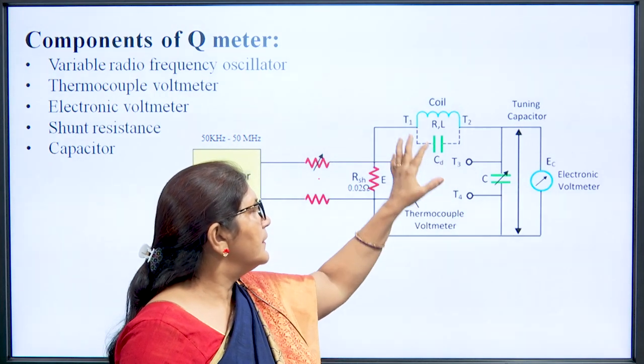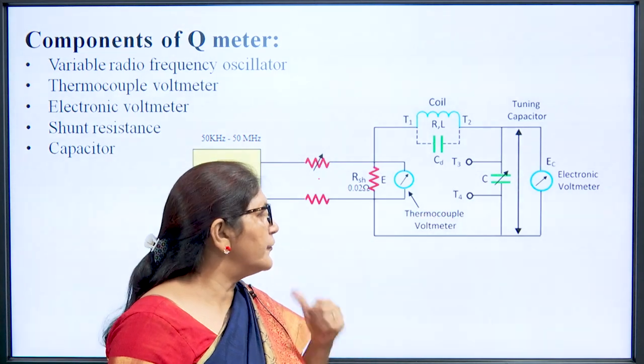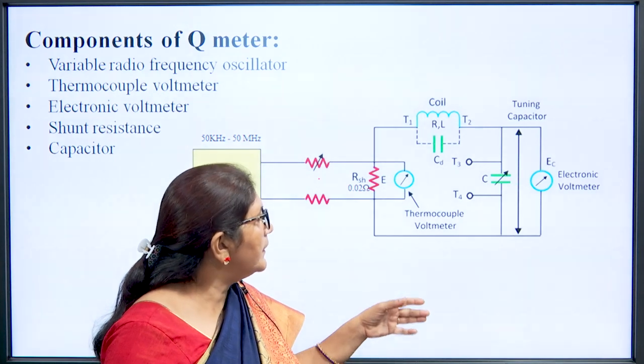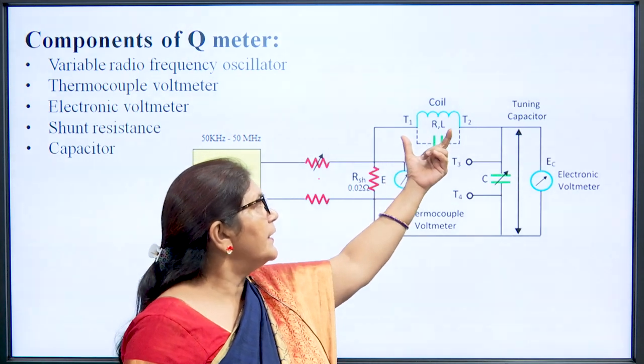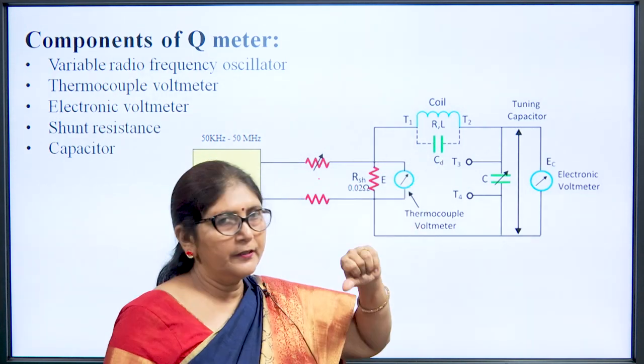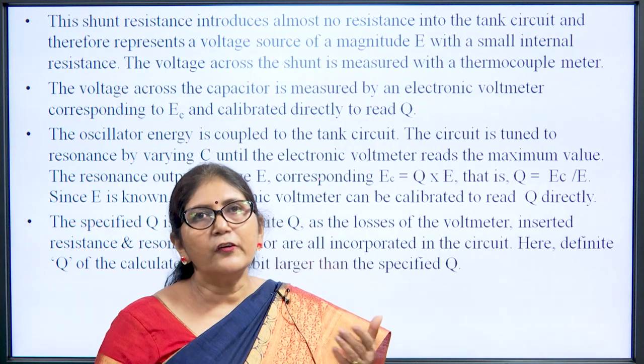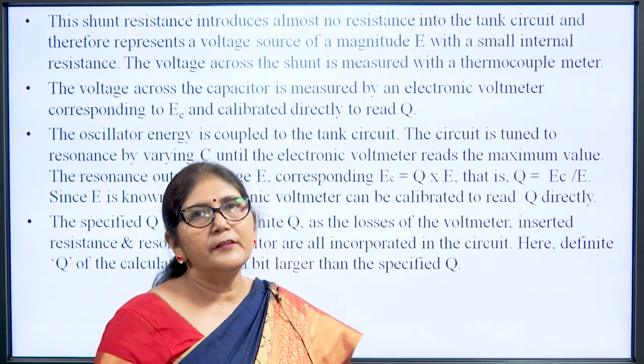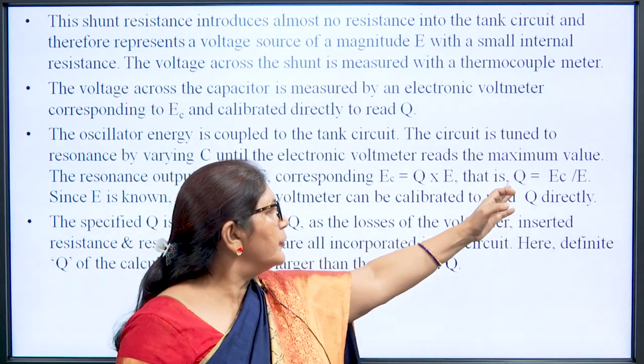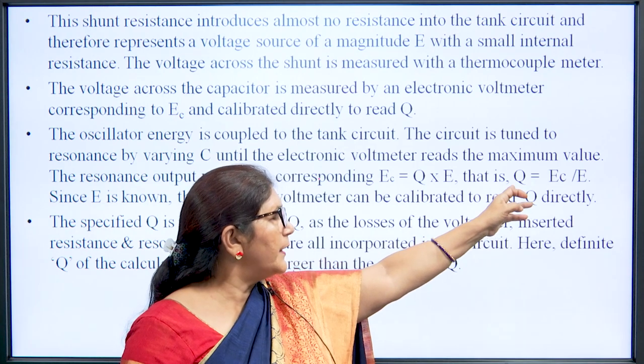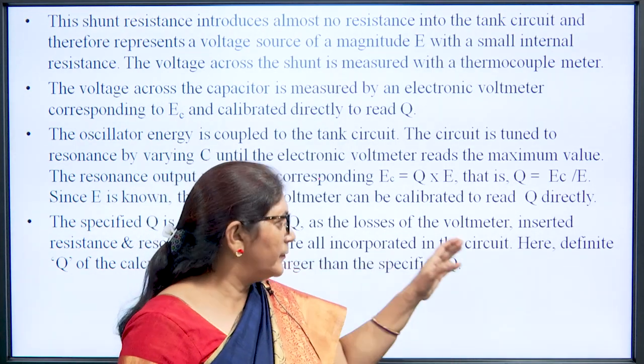There are four terminals in this meter: T1, T2, T3, and T4. When using the shunt measurement method, we connect the coil or capacitor between terminals T1 and T2. The shunt resistance introduces almost no resistance into the circuit. Q is calibrated as EC/E, and since Q is proportional to EC, the meter is directly calibrated in Q and displays the Q value.